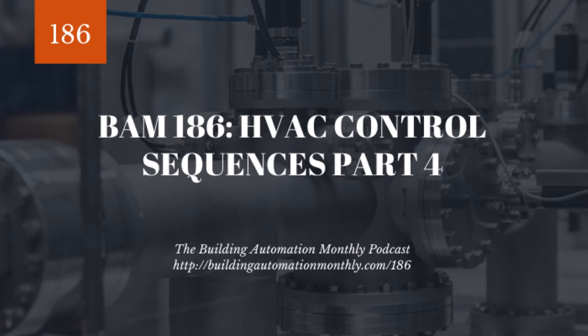There's multiple different states. And what I want you to think about is, what state am I in? What parameters would trigger me to be in that state? And then what should be happening in that state? This will really help you program. This will also really help you troubleshoot. So for example, if you're in a dehumidification state because your return air humidity level or your space humidity level is too high, then you can expect your control system to potentially be doing simultaneous heating and cooling. You can also expect that you're going to be trying to drive the air to saturation. That way you can drain out the moisture and then heat the air back up prior to sending it downstream. That's how typical dehumidification sequences work.